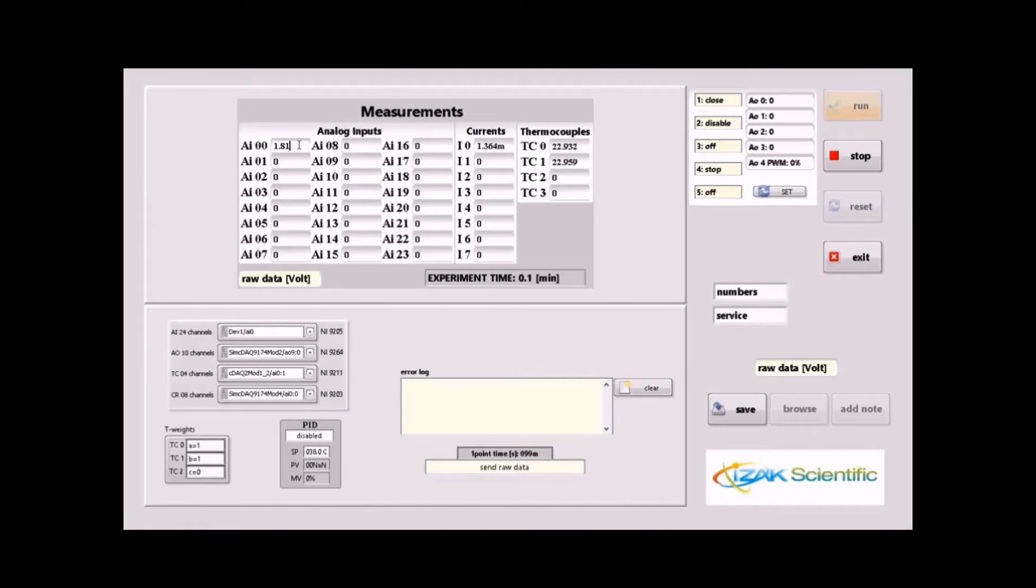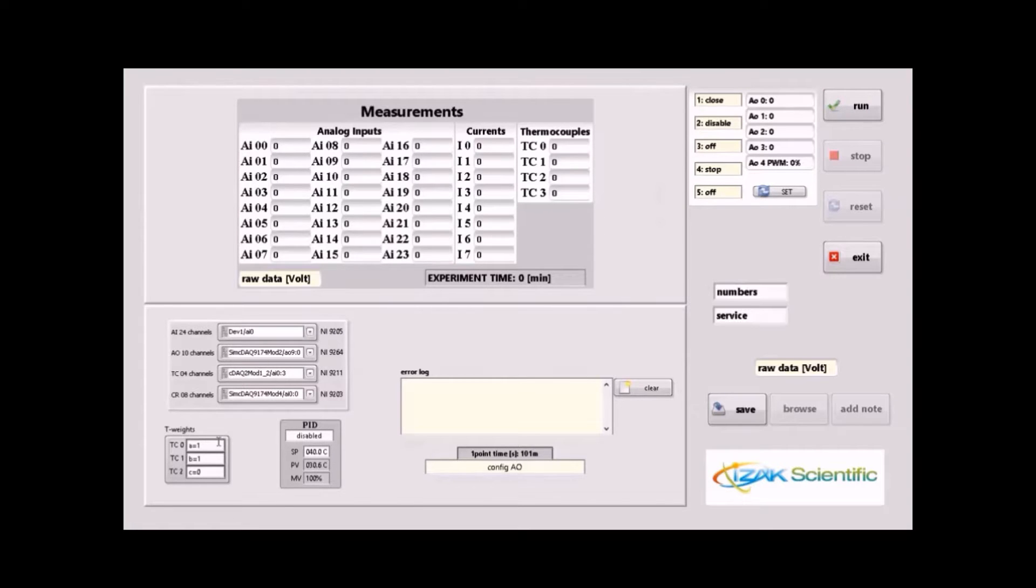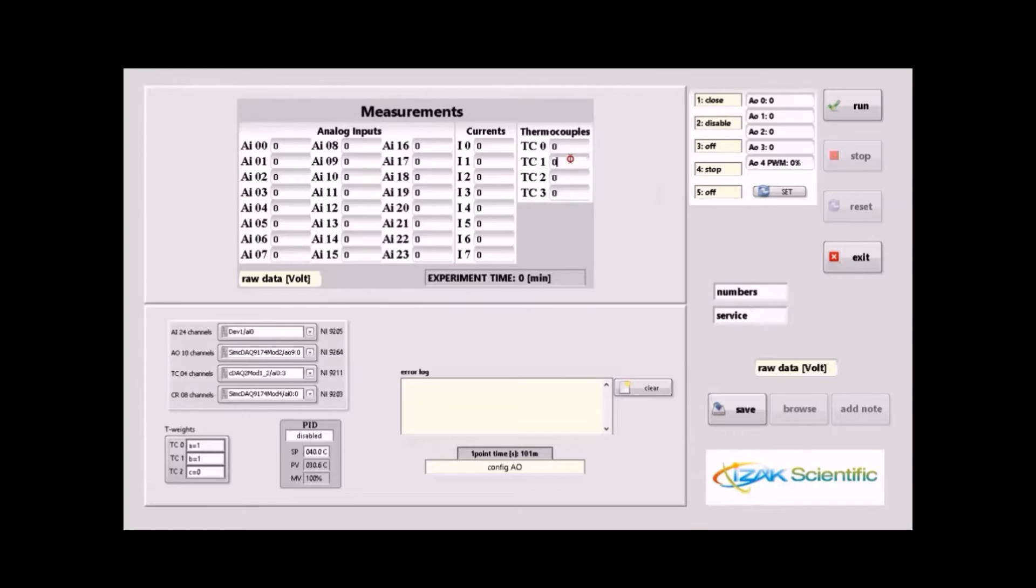In the PID feature, the present value can be determined by the weighted average from up to three different sensors. In this case, we control the temperature, and we set up temperature weights to the thermocouples so the PID is determined according to the weighted average value.